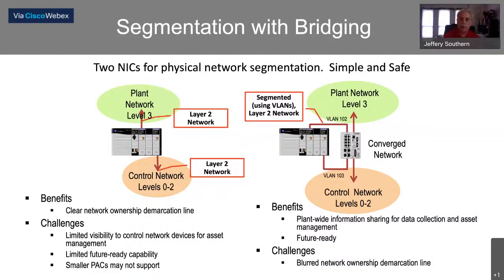We also have segmentation using VLANs, which we'll talk about in a bit. You can combine the idea of two NIC cards with VLANs. The benefit is this is probably one of the most secure ways you can separate things - in fact, there's a rule in control logic that will not allow that message from the plant network to go down to the controls level network unless you specifically tell it to. It's blocked by default.